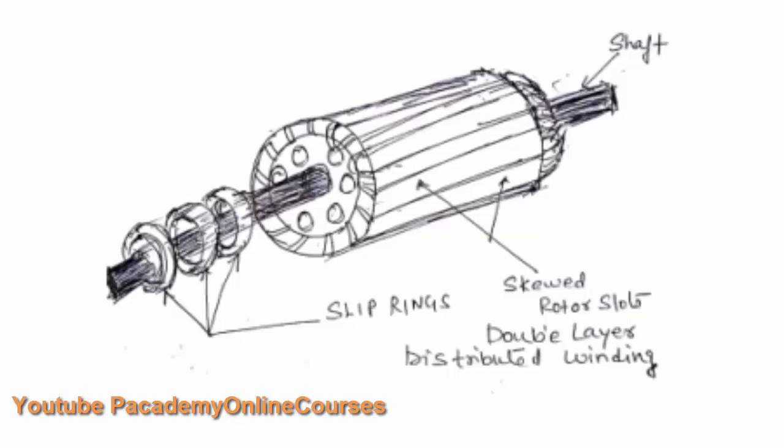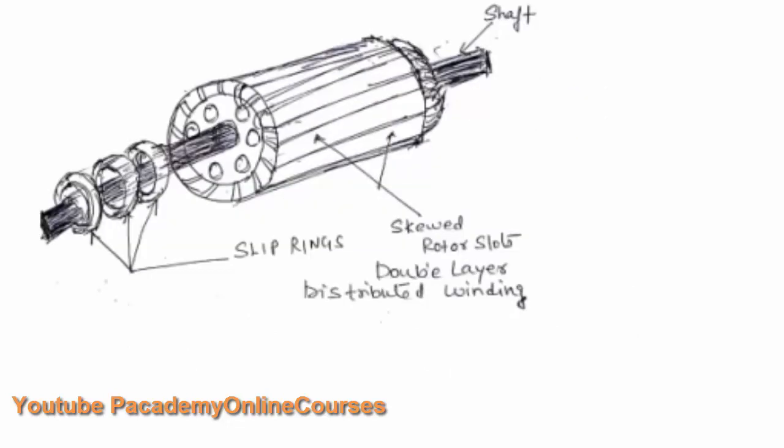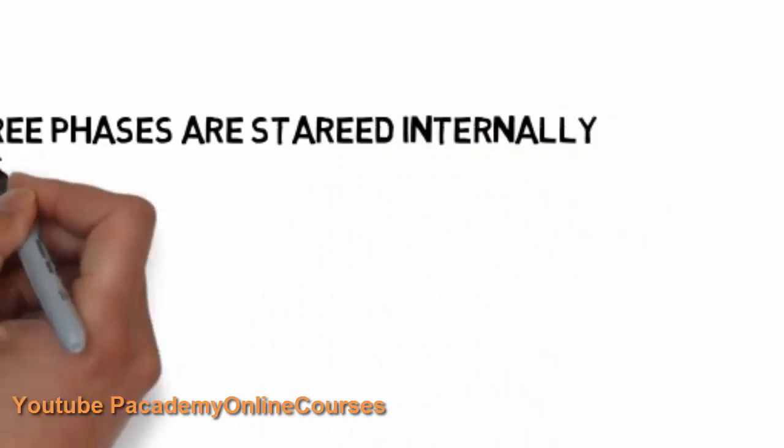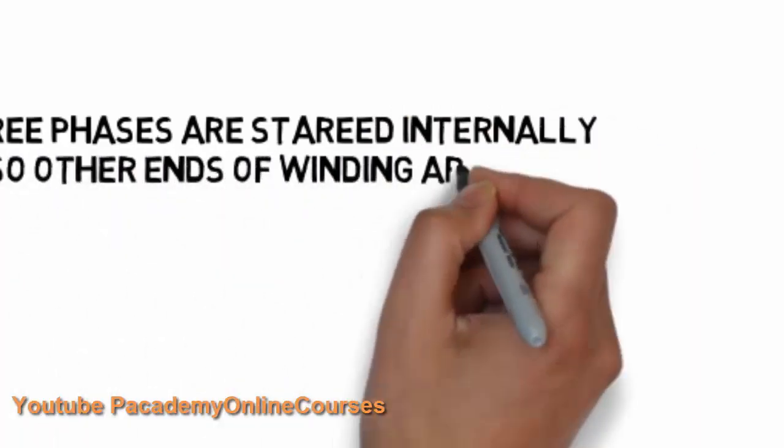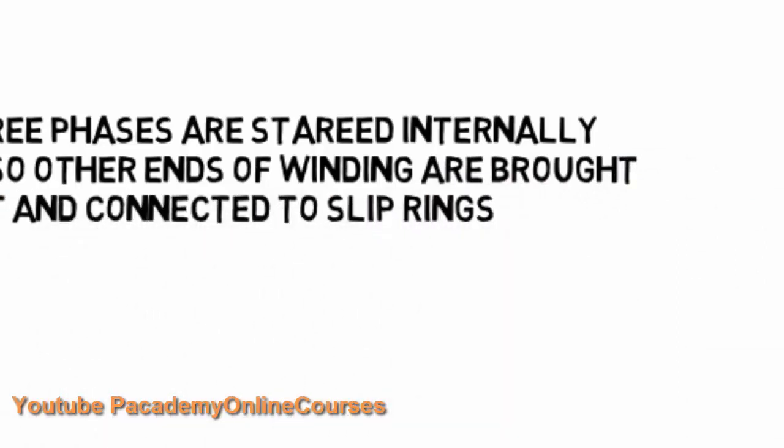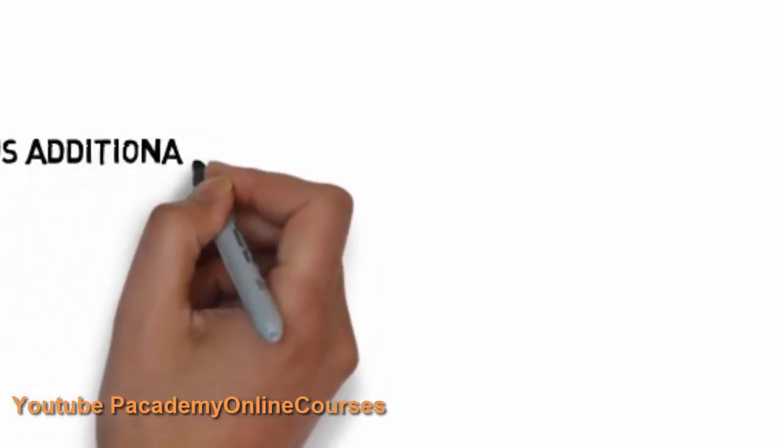The three phases are star connected internally. The other ends of the winding are brought out and connected to the slip rings to the external resistance circuit via brushes. The brushes will be lifted during normal running after the motor starting purpose is fulfilled. Thus addition of starting resistance is possible.